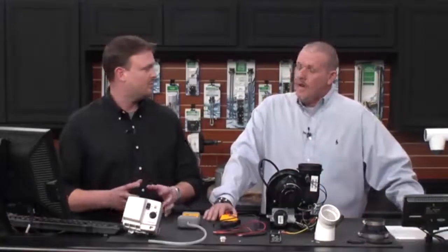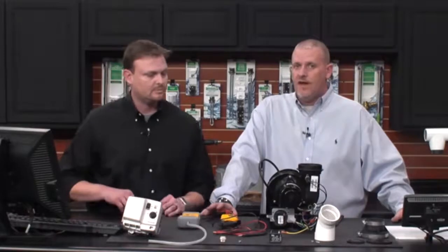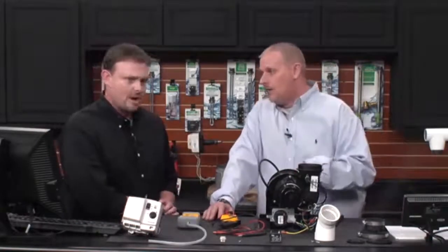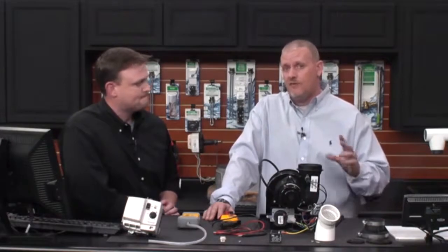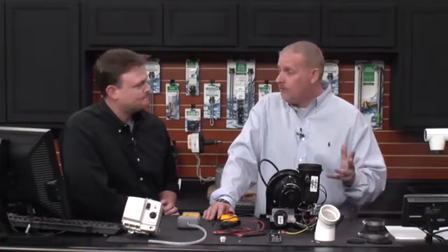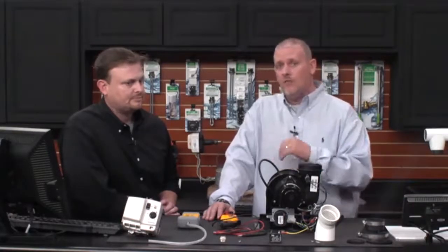We're talking about we lost flame sense, the flame sense rod we were talking about earlier. This 6.3 flash means that somewhere in the heating cycle, we made it past the initial startup. So we know that flame sense took place at least once for us to start this heating cycle. But somewhere in this heating cycle, we lost that flame.